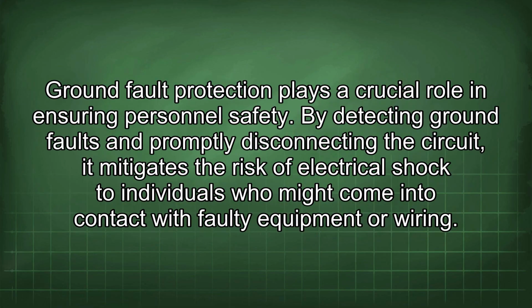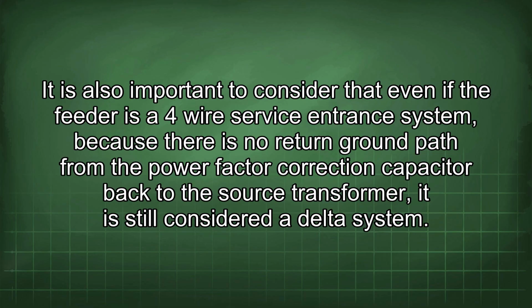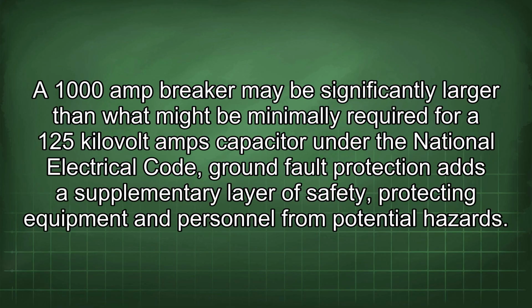Ground fault protection plays a crucial role in ensuring personnel safety. By detecting ground faults and promptly disconnecting the circuit, it mitigates the risk of electrical shock to individuals who might come into contact with faulty equipment or wiring. It is also important to consider that even if the feed is a 4-wire service entrance system, because there is no return ground path from the power factor correction capacitor back to the source transformer, it is still considered a delta system. A 1000 amp breaker may be significantly larger than what might be minimally required for a 125 kVA capacitor under the National Electrical Code.